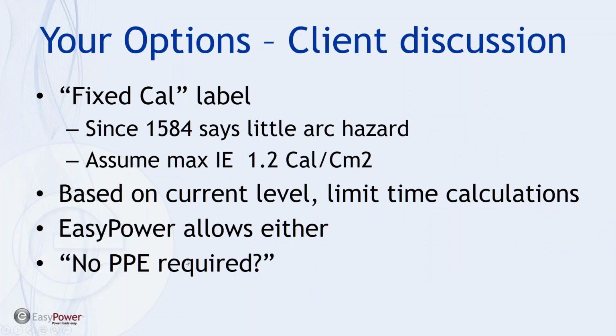All right. The point here, and this just came up last week, is someone doing something like this and making the comment that no PPE is required because the bus incident energy falls below 1.2 calories. Now, I personally think this is a misreading of the fact that NFPA 70E has done away with category 0. Below 1.2 calories per square centimeter, they're not saying there's no arc flash potential. They're saying that 1.2 calories is the point at which there's a 50% chance of a second-degree burn to exposed skin. So if I have no PPE on, there is still a potential for me to receive burns. And so I would be careful using this terminology.